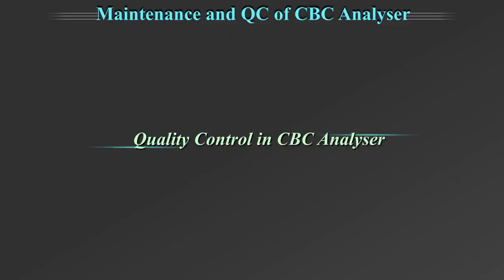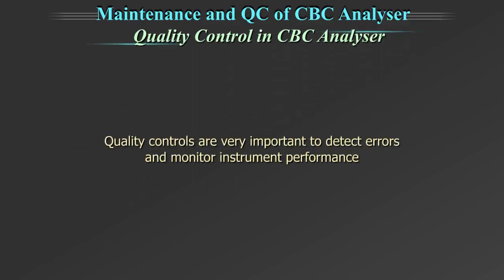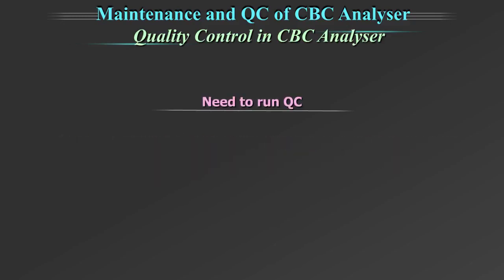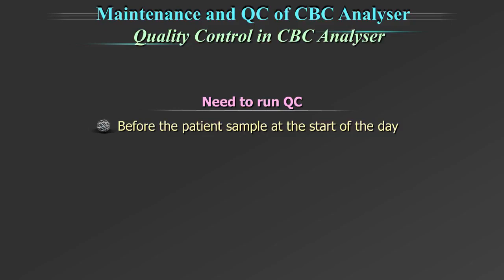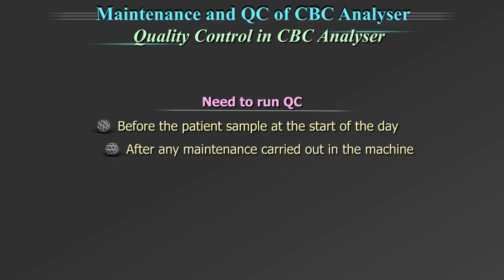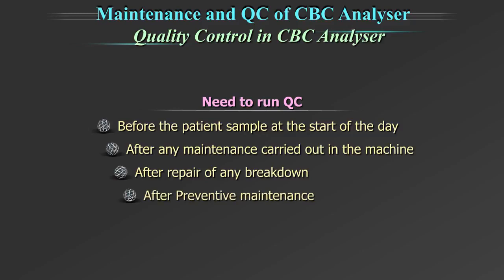Quality control in automated CBC analyzer. Quality controls are a very important part of achieving result accuracy and monitoring the instrument performance. They need to be run before the patient sample at the start of the day, after any maintenance carried out in the machine, after repair of any breakdown, and after preventive maintenance.